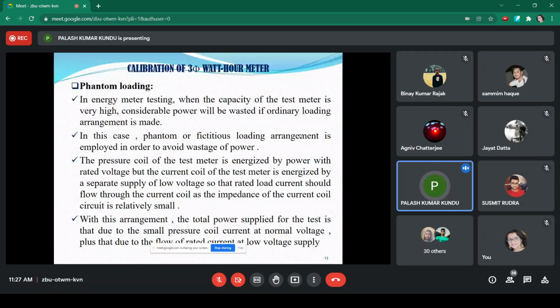Now, the phantom or fictitious loading arrangement can only be done in the case of wattmeter or energy meter calibration. That avoids the wastage of power. With this arrangement, the total power supplied for this test is that due to the small pressure coil current at normal voltage, plus that due to the flow of the rated current at the low voltage supply. Generally, in the phantom loading method, the power supply for the current coil should have a very small value, but the rated voltage of the supply required to excite the potential coil is a high value. That is the condition.